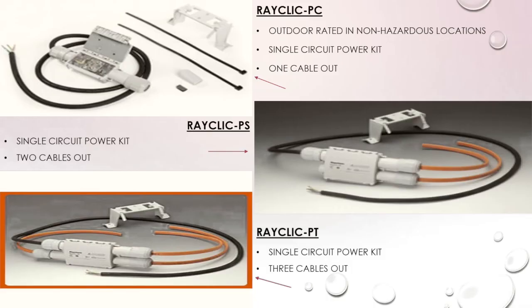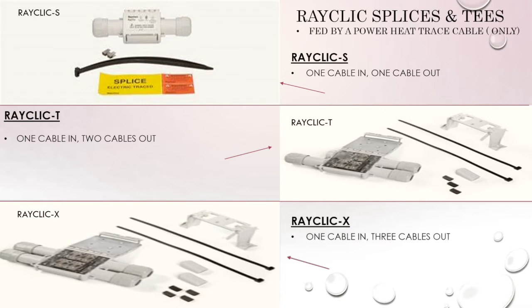Now switching to commercial components — our RayClic series. The RayClic series is rated for outdoor and indoor use in non-hazardous locations, and all power kits are single circuit. The RayClic PC is the most common: one circuit, one cable out. The RayClic PS has two cables out, and the PT has three cables out. For splices and Ts, the RayClic S is one cable in, one cable out, and the RayClic T is one cable in, two cables out.